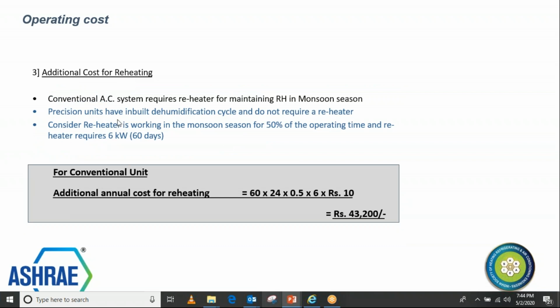Now here the cost of reheating, you can see, again, we have considered only for the 2 months, but only 50% of the time the heater is working in monsoon. This impact can also come when your system was cooling and dehumidifying, and then the heater does not understand. The heater is just trying to know that only the temperature has gone down, and it is just trying to adjust the heat of the air. So when your systems are working independently, it doesn't know what's happening with the other component. Unlike in precision AC, where all the components are integrated and your systems only allow the component which is required as per the room cooling requirement, or humidification or dehumidification requirement, or heating requirement.